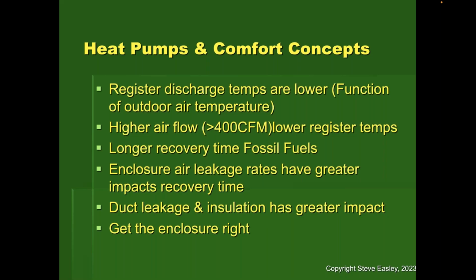Okay, yeah. So the new rating is going to be more efficient. Keep in mind, the reason the new rating was developed was because they recognized that the way these systems are typically installed in homes, the ducts have a lot more restrictions than the initial test really showed. So the old method of measuring efficiency made them look like they were more efficient than they really were in the real world. So they made this adjustment so that these would have more real world efficiency.